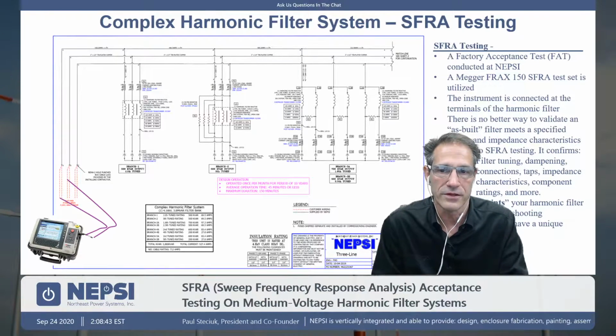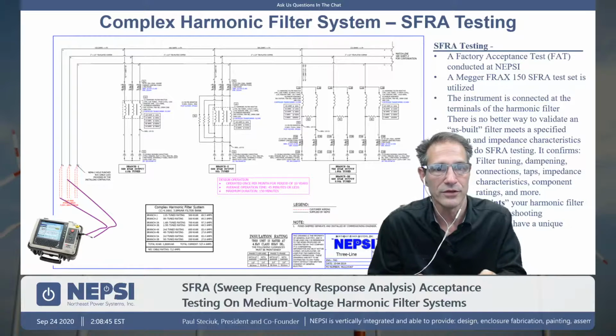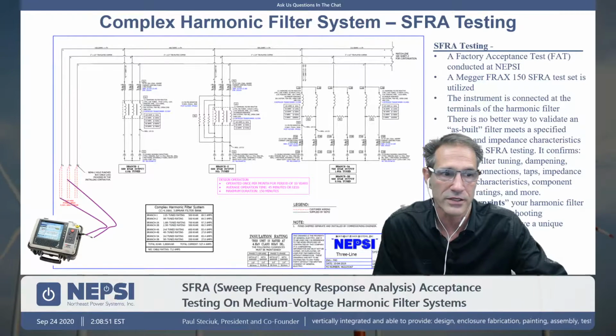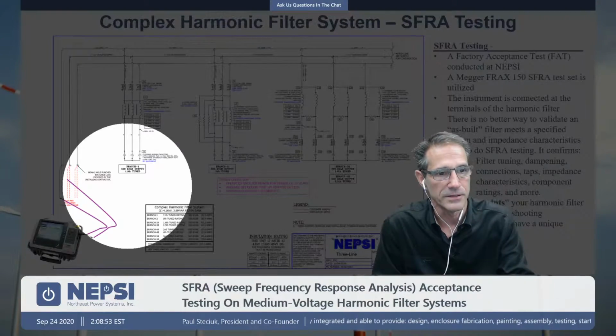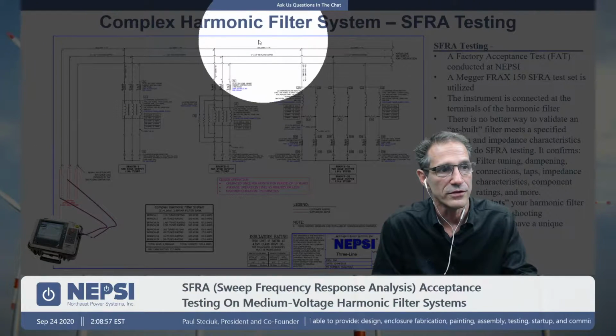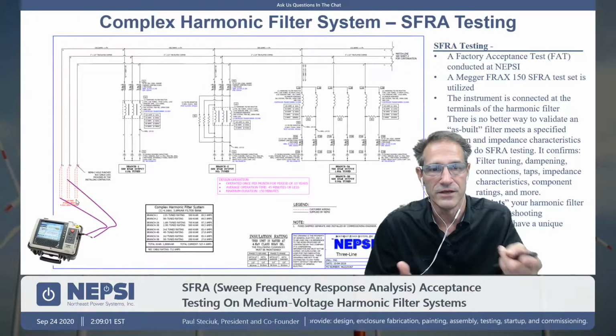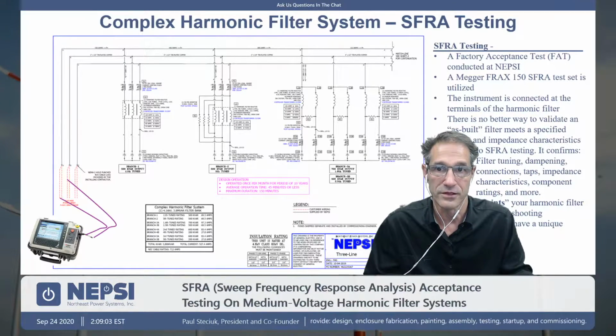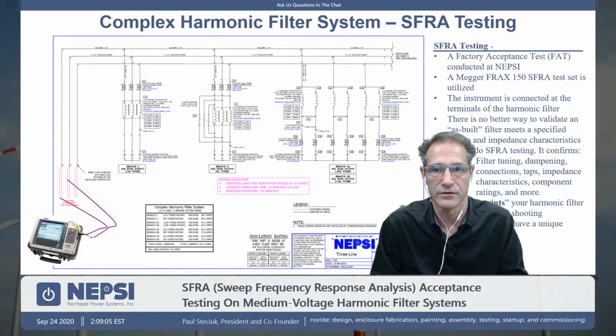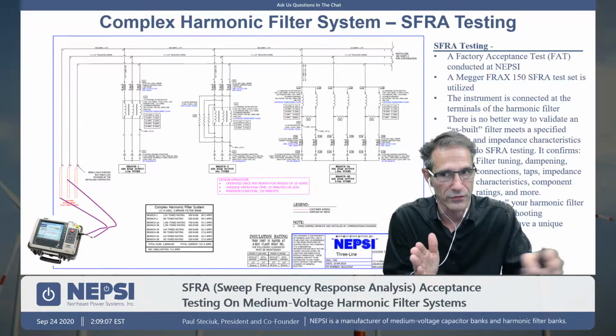Well, NEPSI investigated about 2 years ago, well, perhaps we can use this instrument to test our harmonic filters. Because really what this instrument is doing is injecting a current into the filter here, and it's reading a voltage across this terminal. So essentially it's taking V divided by I, and it's calculating the impedance of the harmonic filter. And it's doing that through a range of frequencies.